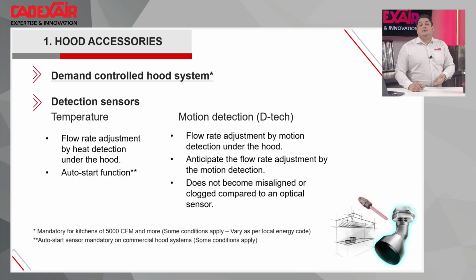So this is what we like also about the system: the D-tech cannot be misaligned, as an optical sensor can, and it also cannot be affected if it's dirty, because optical sensors are, and we live in a hood, so they're always full of grease. It will not be dirty. You don't have to wash the lens. You can put 1 inch of grease all around the D-tech sensor and it will still operate, because it's like a wave, like a radar, that they use with that kind of system.